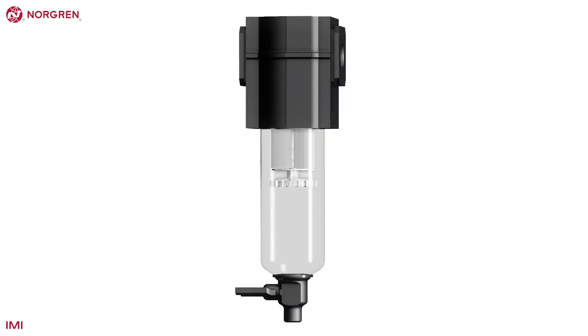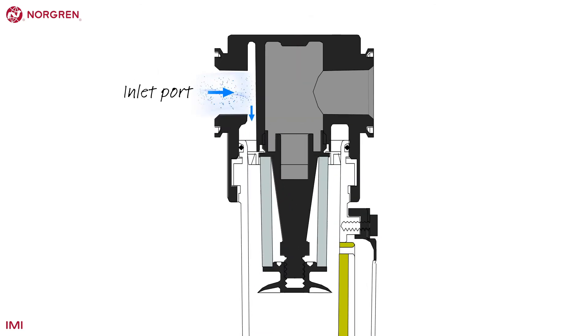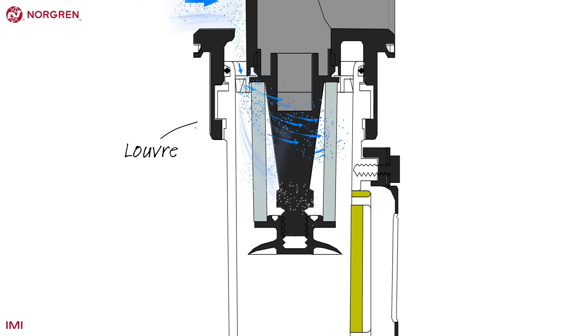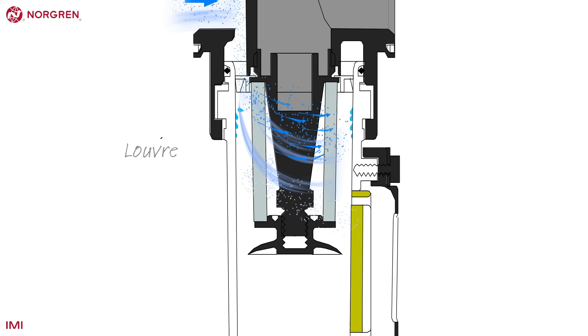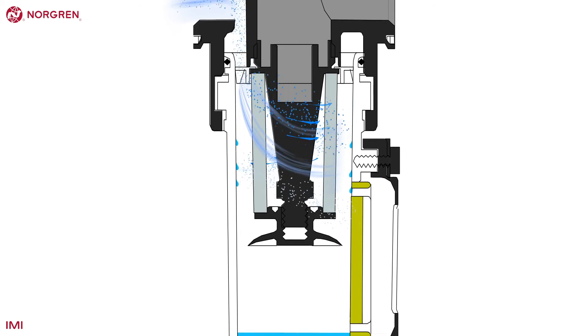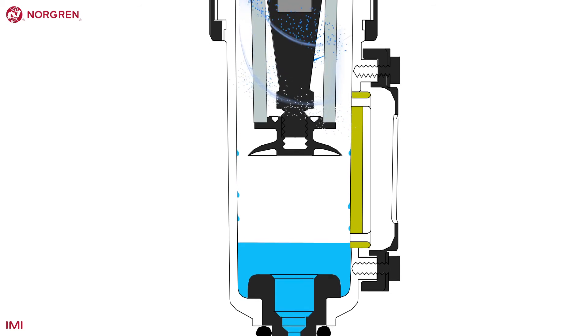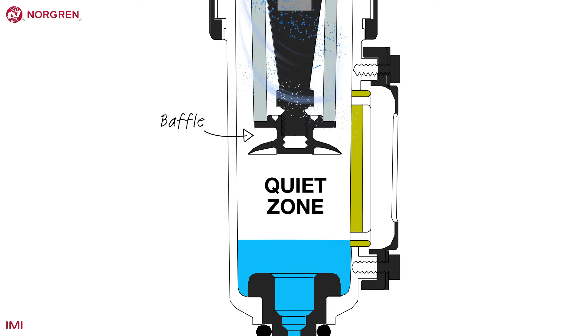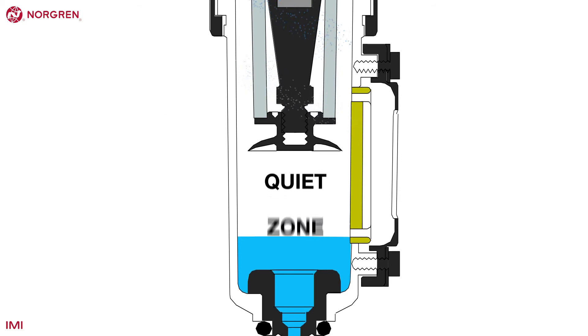Let's see how it works. The air enters the inlet port on the left before it hits the solid wall and is directed downwards. Any very large particles or water droplets will lose their momentum as they hit the wall and fall into the bowl below. As the air continues to move into the filter, it moves across the angled fins of the louvre, causing a cyclone effect. Momentum forces smaller water droplets to the outside of the bowl and gravity causes them to collect at the bottom. While the air is very turbulent above it, the baffle creates a quiet zone below it where the air isn't spinning.